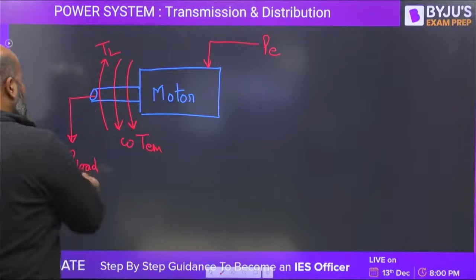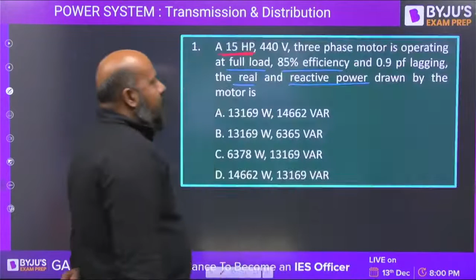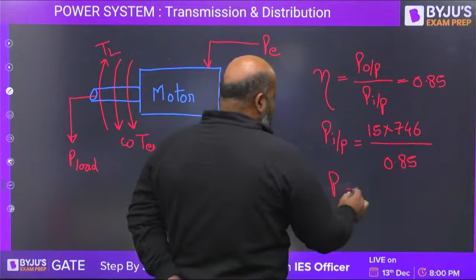The output of the motor is mechanical power. If you see the question, the power rating is given in horsepower. It means he is giving you the output of the motor. So if you know the efficiency, you can write output upon input. The efficiency given is 85%, so this is 0.85. From here you can find the real input power, because efficiency relates to the real power, not the reactive power. Output is given as 15 horsepower. So 1 horsepower is approximately 746 watts, divided by 0.85. To solve this, you will get the real power input taken by the motor from the supply.